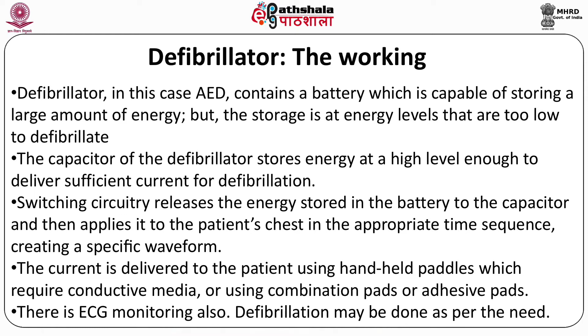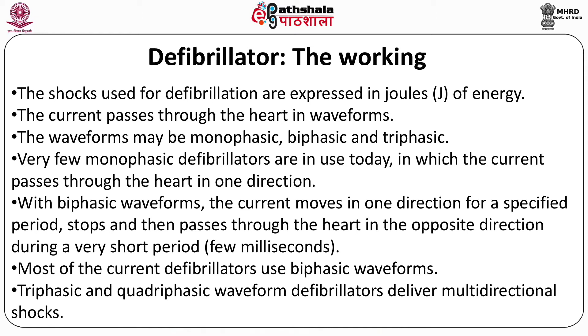Defibrillator, the working. The shocks used for defibrillation are expressed in joules or J of energy. The current passes through the heart in waveforms. The waveforms may be monophasic, biphasic and triphasic. Very few monophasic defibrillators are in use today, in which the current passes through the heart in one direction. With biphasic waveforms, the current moves in one direction for a specific period, stops and then passes through the heart in the opposite direction during a very short period, say a few milliseconds. Most of the current defibrillators use biphasic waveforms. Triphasic and quadriphasic waveform defibrillators deliver multidirectional shocks.